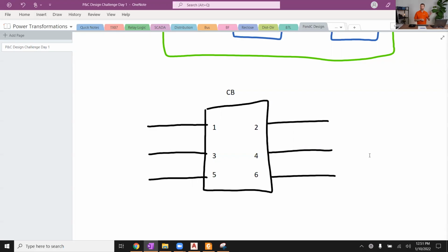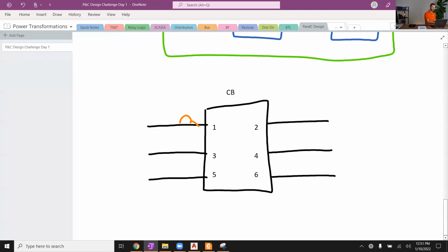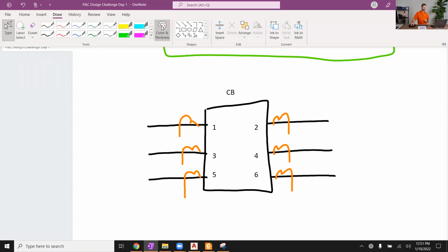So always remember 1, 3, 5 side of the breaker or 2, 4, 6 side of the breaker. It's not 1, 2, 3, and 4, 5, 6. It's 1, 3, 5, 2, 4, 6. And what about the CTs on these breaker bushing CTs? We oftentimes will have CTs on both bushings or both sides of the breaker. What about the polarity dots?